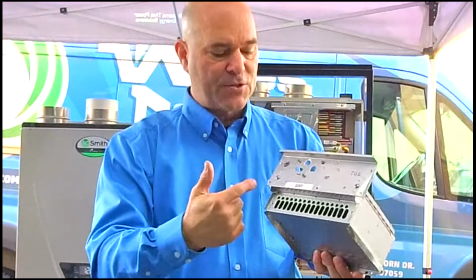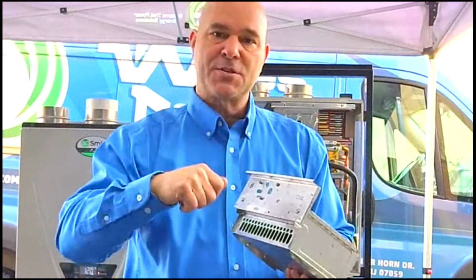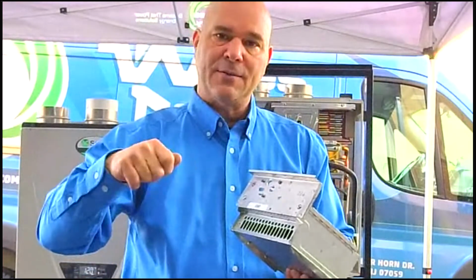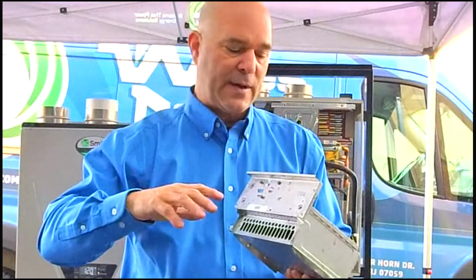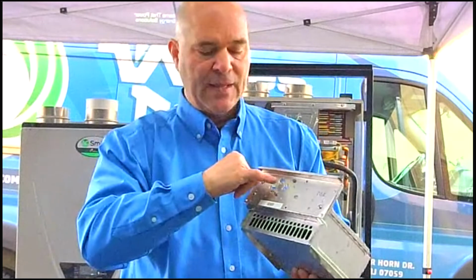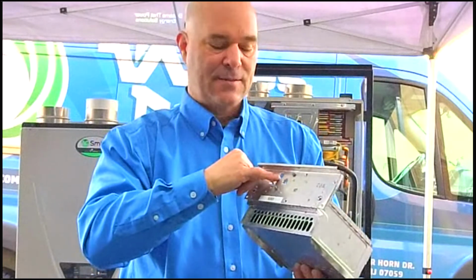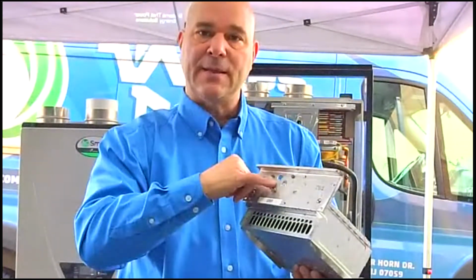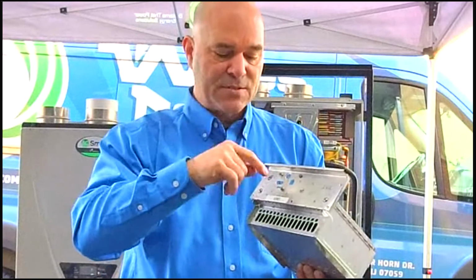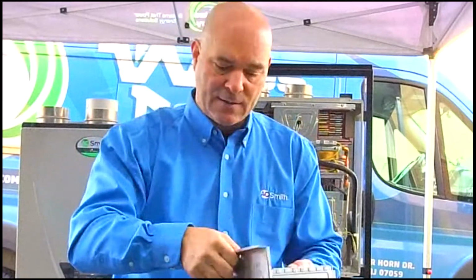If you take this burner tray out, you're going to wash it with soap and water. You'll blow it out after you're done. Make sure you have all the water out of it. It's dry, ready to go back in. Make sure that glass is still in there, the little sight glass. It locks in, but just check it. I've seen one of those fall out when a guy was washing it.